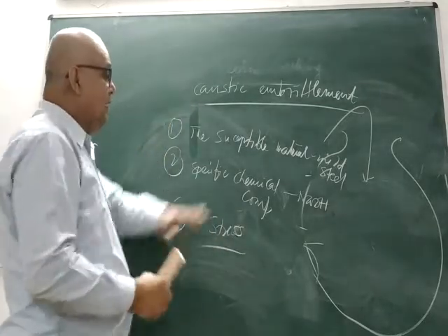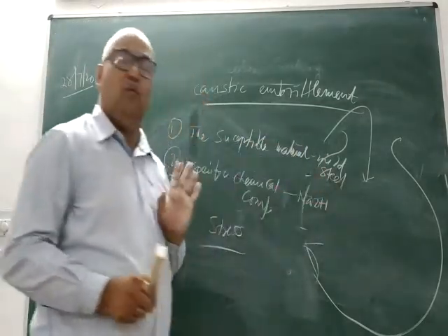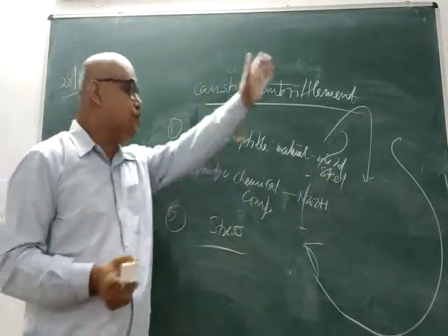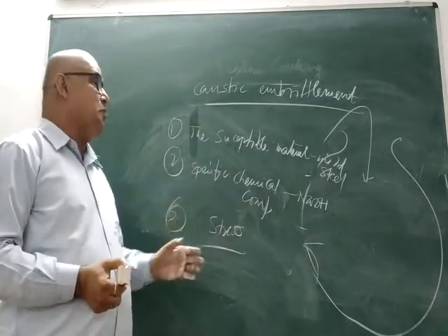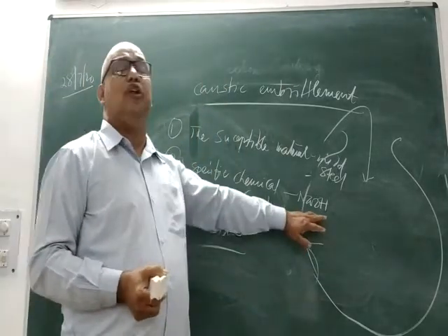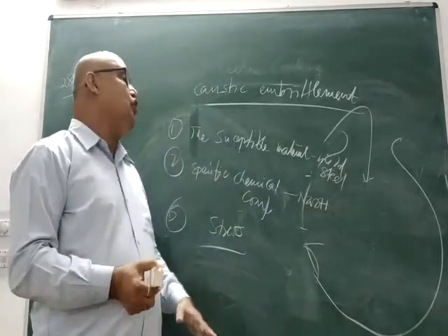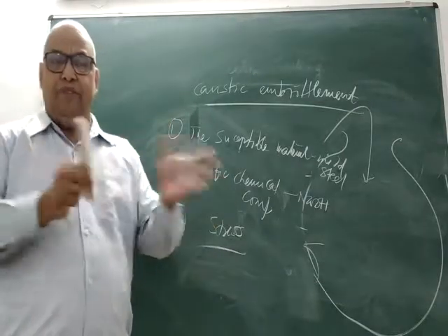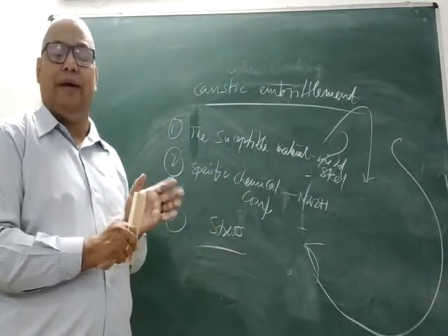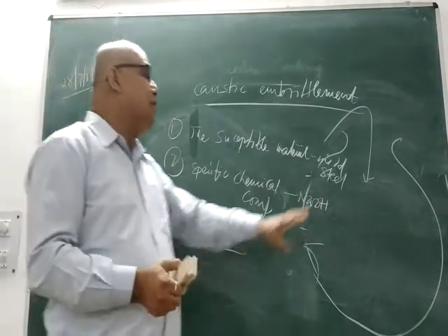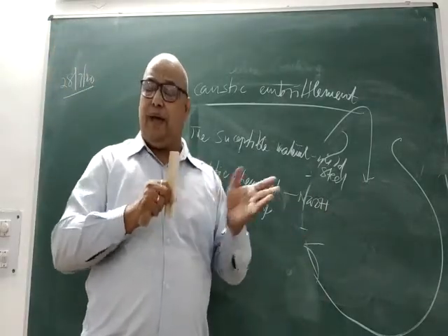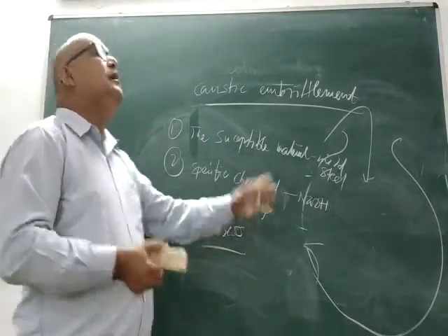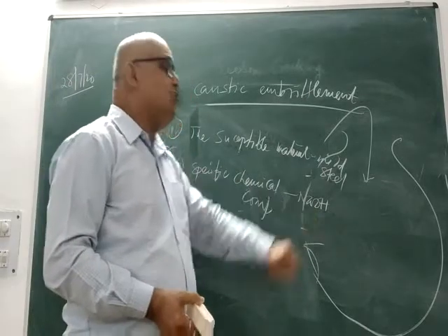You see, your boiler is made of mild steel, so one condition is fulfilled. Sodium hydroxide, I have told you, the water being used over there may directly contain sodium hydroxide, or it may not contain sodium hydroxide as such, but there is a possibility that during treatment of water we have used sodium carbonate, and therefore the water may contain sodium carbonate. During boiling, we have seen sodium carbonate will in turn make your water alkaline by converting into sodium hydroxide.